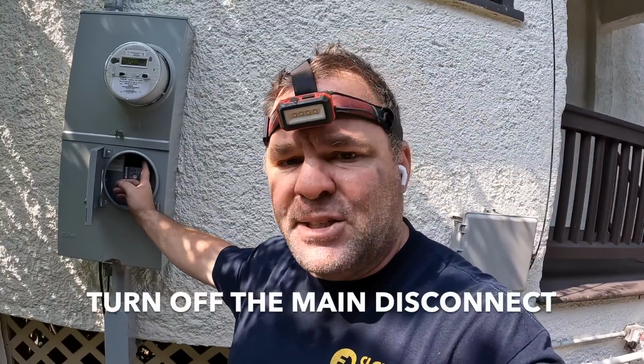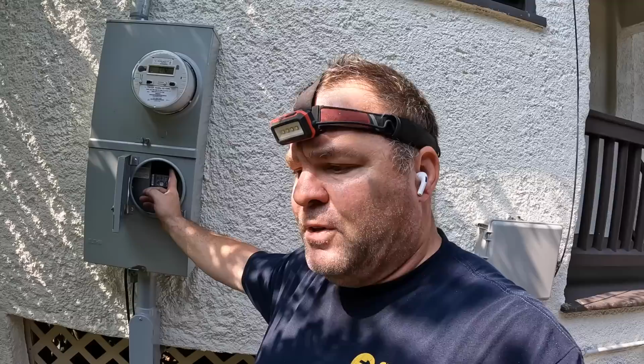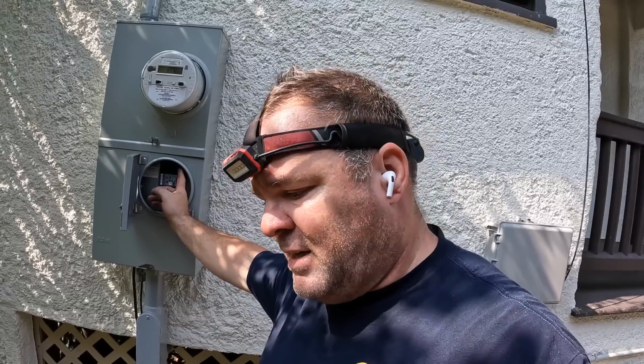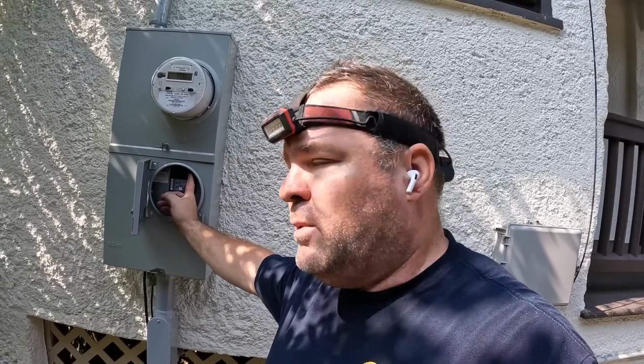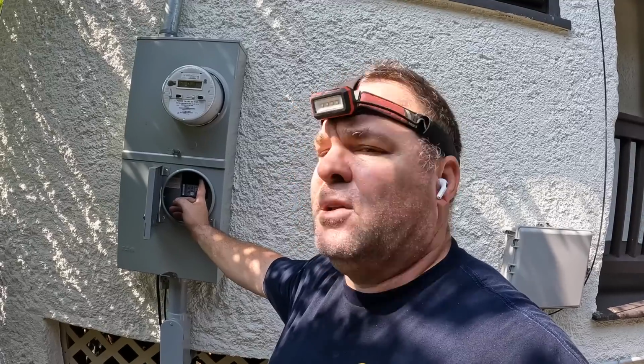All right, so the last thing I want to check here before I can say this is complete, well it's not going to be complete until we tear down the old service. What I want to try now is to make sure the generator turns on when power is lost, since we did work on the transfer switch. So I'm going to turn off the main disconnect and wait for the generator to start, then go inside to see if it transferred the load. Then we'll come back out and turn this breaker back on, and we'll know a load test was done and the generator is working efficiently.